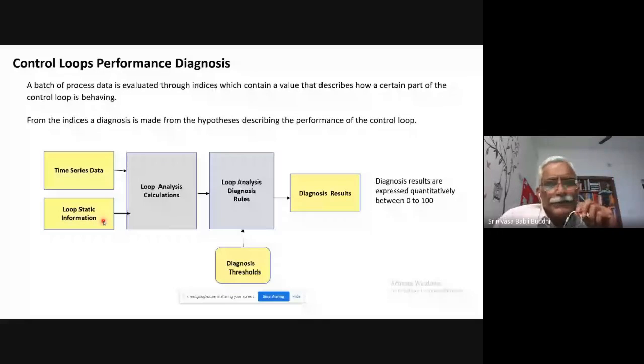So typically what we do is, once we collect this data from all the process signals, as I mentioned, a batch of process data means if I collect data at 5 seconds, at the end of the shift I have batch data for about 8 hours. Okay. So I use this 8 hours of process data and do a lot of computations, and we have different types of indices which tell us how a certain part of the control loop is behaving.